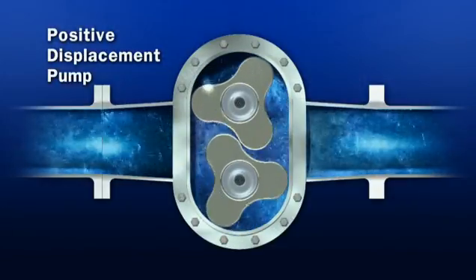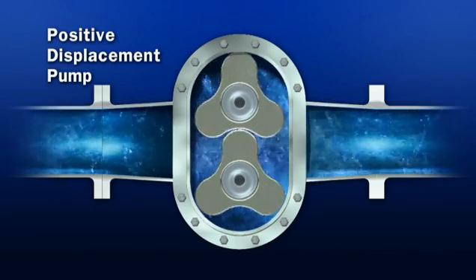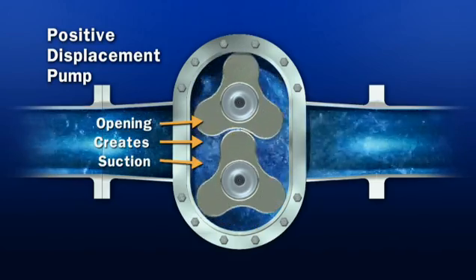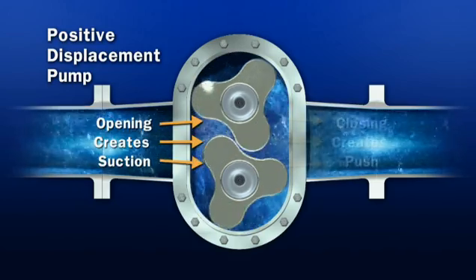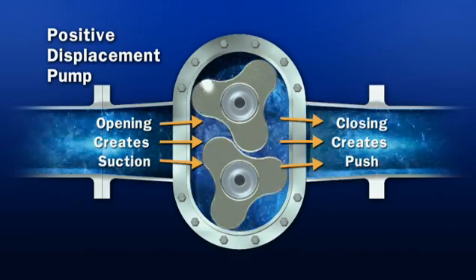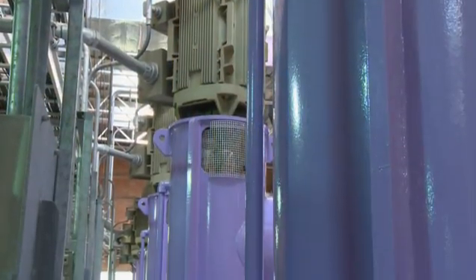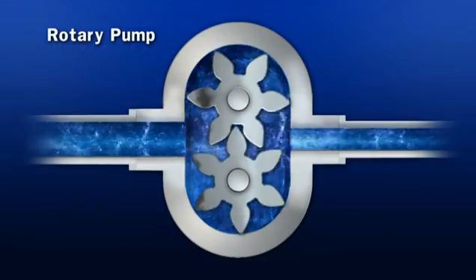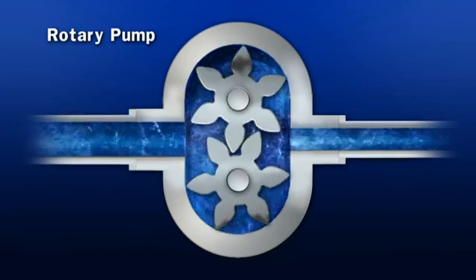Rotary pumps use rotating pump elements to move a known volume of liquid through the pump. PD rotary pumps will put out a constant volume of liquid regardless of the pressure and do not impart velocity to the pumped liquid. Metering is accomplished with rotary pumps by a calibrated pump element that creates a cycle count of revolutions and moves a dial or is recorded electronically.